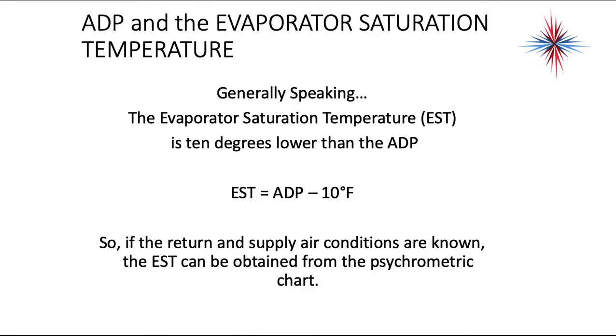The ADP and the evaporator saturation temperature are related. Generally speaking, the evaporator saturation temperature, or EST, is 10 degrees lower than the ADP. So if you know your return air temp and wet bulb temp, and your supply air dry bulb and wet bulb temp, you can calculate your ADP by extending that line out. Once you know that, you can figure out your evaporator saturation temperature, which helps in troubleshooting cooling issues.